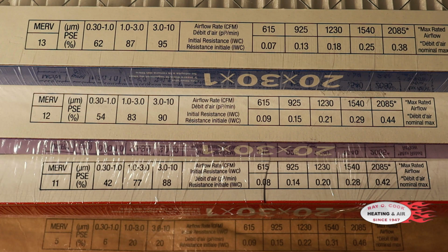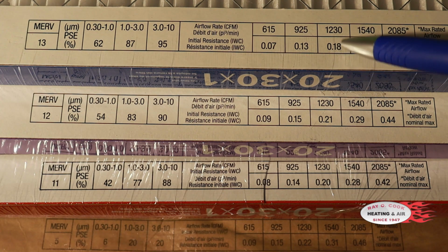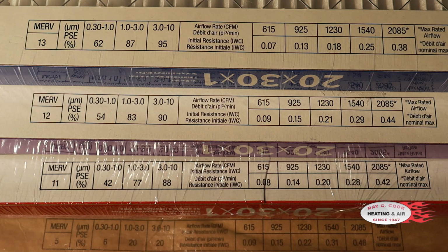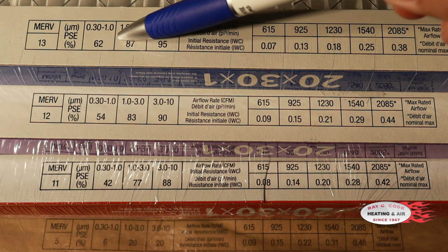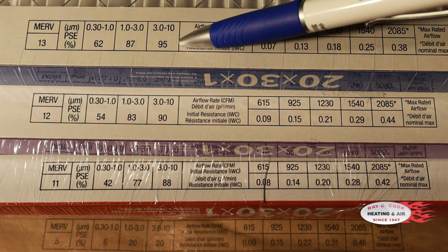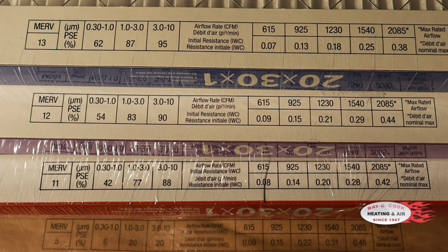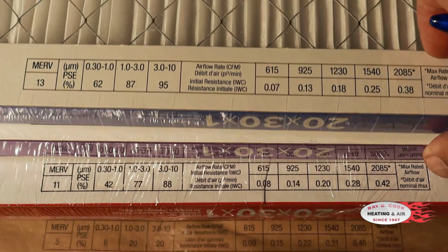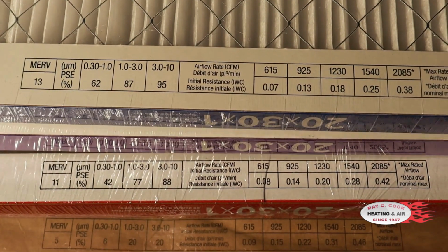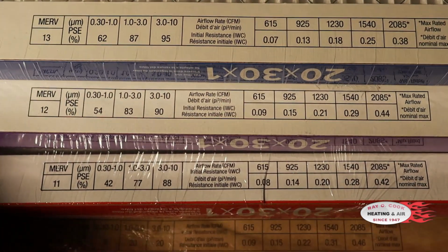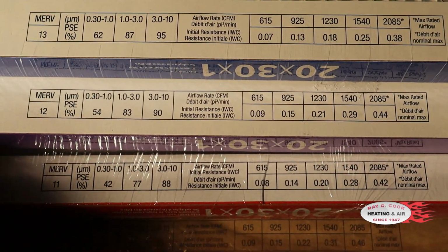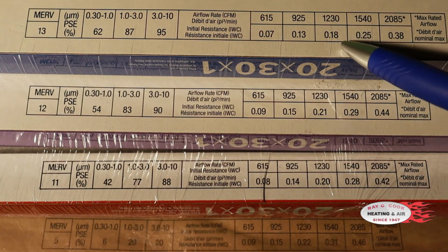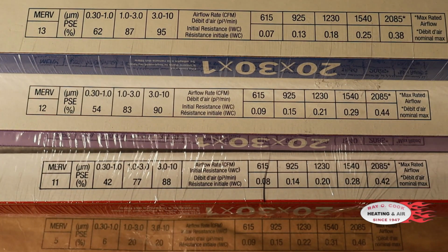So as this filter gets dirty, that resistance will go up and the airflow will go down, and it will happen quickly on these type of filters because they're only 1 inch thick. So for instance, this MERV 13 that's grabbing all of these particles at a very high rate, it doesn't have a lot of place to put them because it's only 1 inch thick. Even though it is pleated, okay, that helps some. However, when they say 90 days on this filter, I would be very careful with that because you're already, for instance, on a 3-ton unit, you're already up against the pressure that we don't want to exceed.